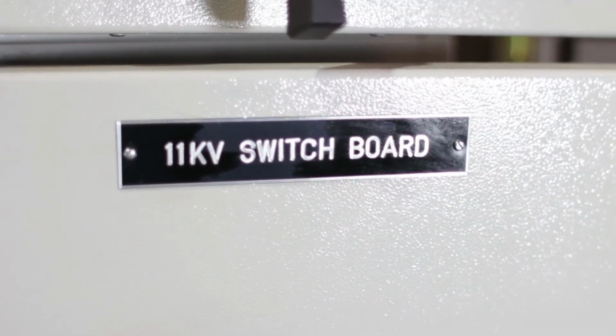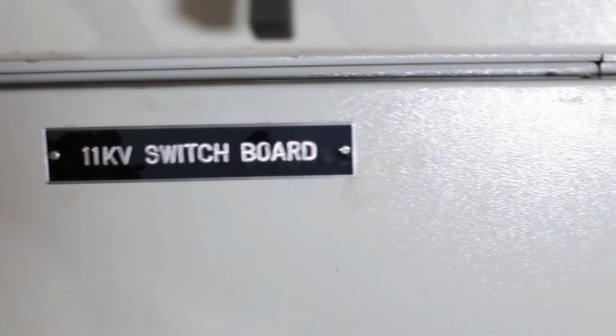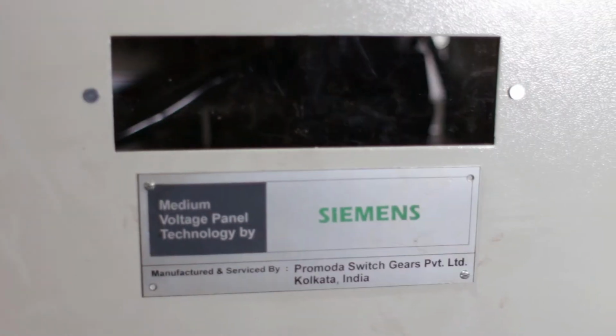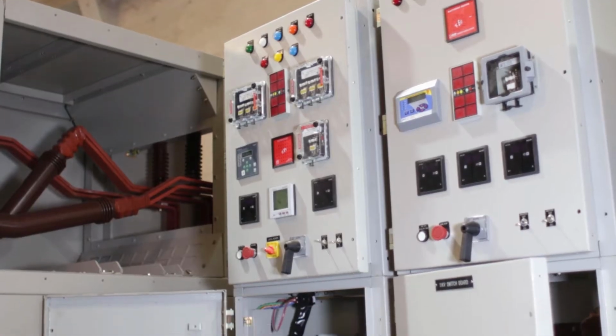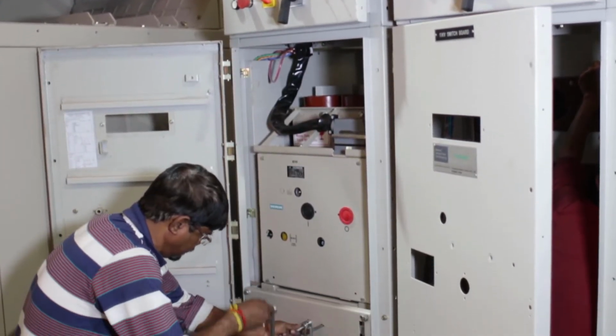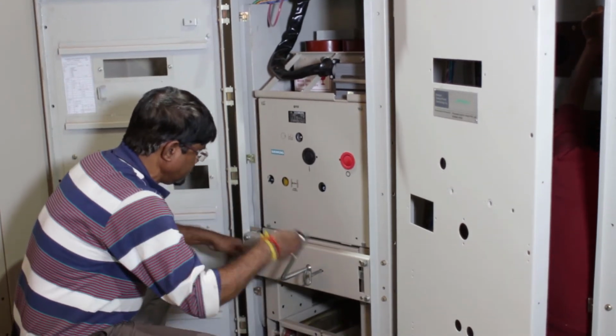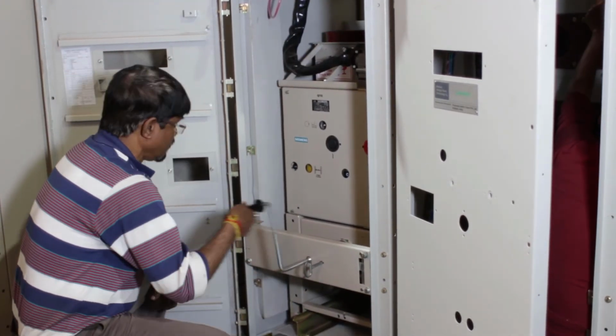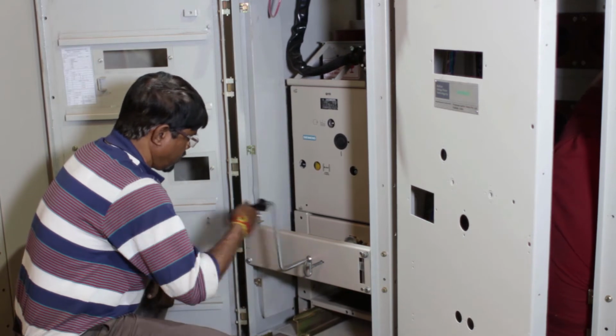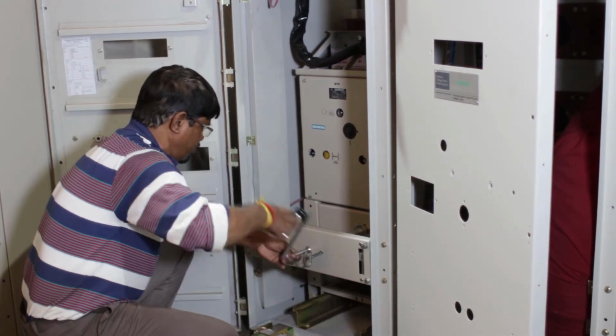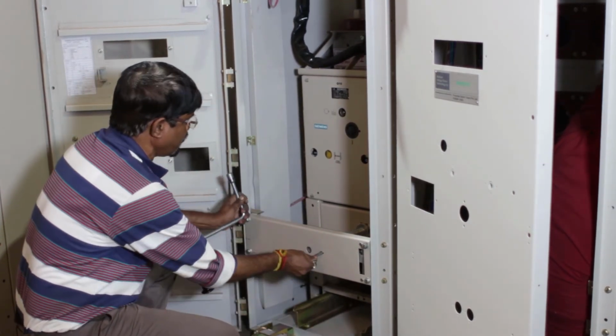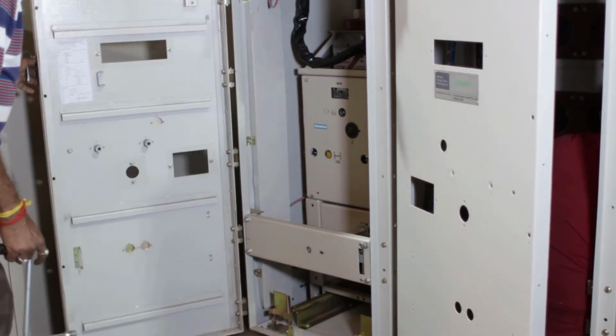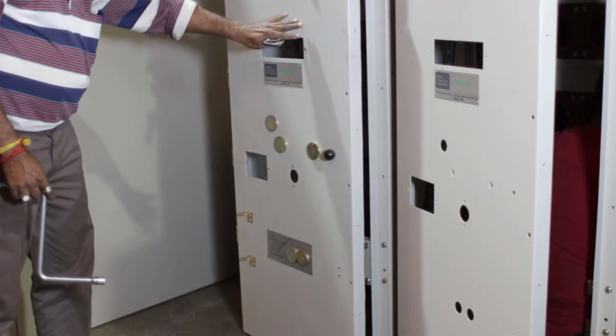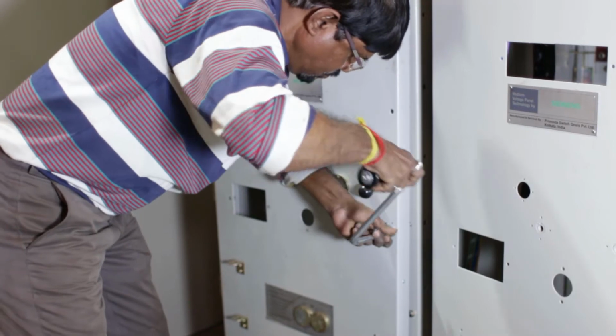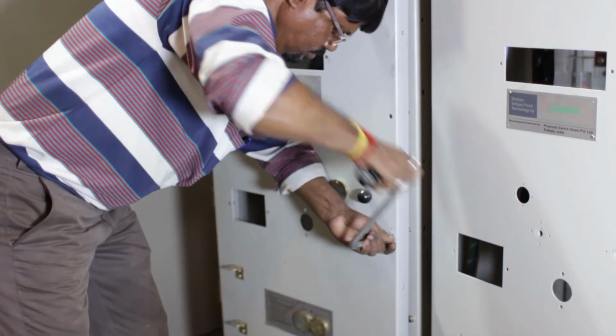11 kV VCB, similar to 33 kV, is also compartmentalized in design with the advantages of lowest arc energy dissipation, lowest drive energy requirements, no fire hazards or explosion risk as the panels are type tested for internal arc tests, least number of moving parts and hence highest reliability. The 11 kV VCBs are rated for 11 kV 800 ampere 26.3 kA, 11 kV 1250 ampere 26.3 kA to 40 kA, 11 kV 1600 ampere 26.3 kA to 40 kA.